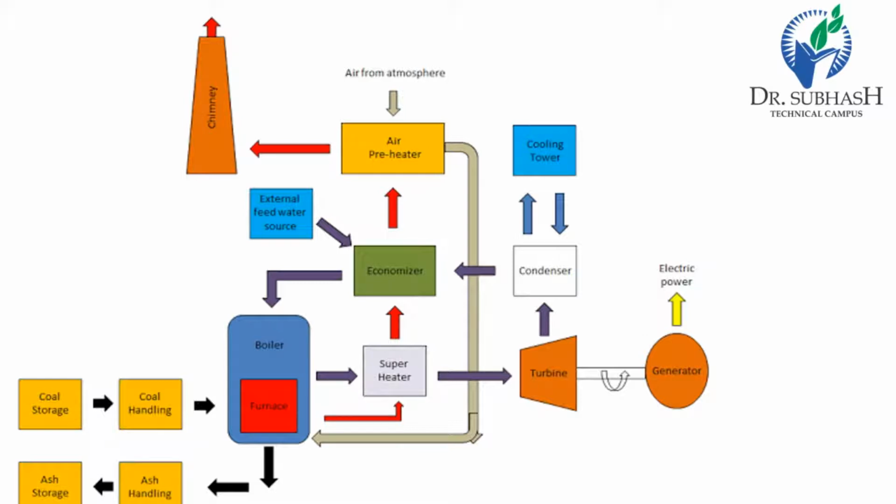After the economizer, the air preheater. An air preheater increases the temperature of air supplied for the coal burning by deriving heat from flue gases. Air is drawn from the atmosphere by a forced draught fan and is passed through the air preheater before supplying to the boiler furnace. The air preheater extracts heat from the flue gases and increases the temperature of air used for the coal combustion.